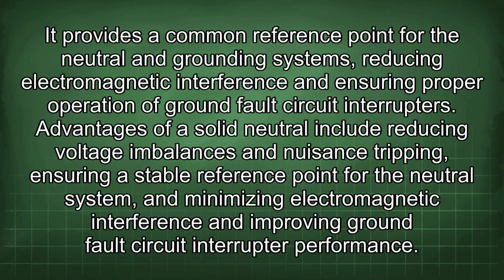It provides a common reference point for the neutral and grounding systems, reducing electromagnetic interference and ensuring proper operation of ground fault circuit interrupters. Advantages of a solid neutral include reducing voltage imbalances and nuisance tripping, ensuring a stable reference point for the neutral system, and minimizing electromagnetic interference and improving ground fault circuit interrupter performance.